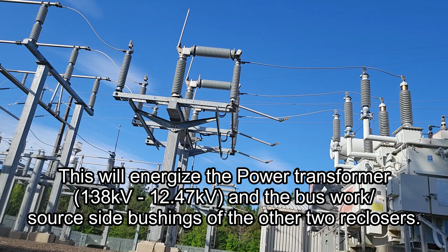So unfortunately, that's the only footage I got. But just to close out the video, my next steps were to energize the remaining 2 good reclosers. Same thing from inside the switchgear. Pushed a button, and we energized them one at a time. There was about 80 amps on each one of those reclosers. And then with the 3rd recloser that was feeding maybe another 900 customers, I went out in the field and closed in a gang switch, a tie switch that was normally always in the open position. We closed that switch, which immediately picked up the other 900 customers or so.